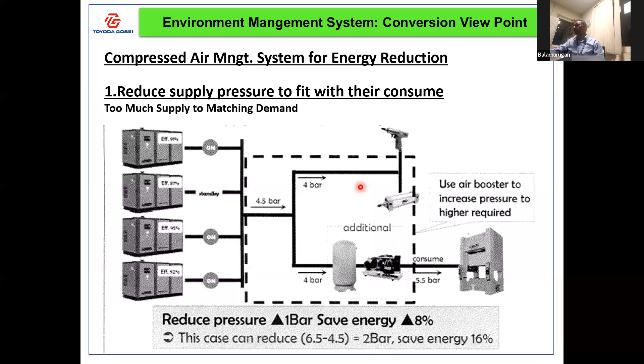So only for that equipment you need a higher operating pressure, so that the load on the main compressor comes down. This will give big energy savings, and we have experience of 16% energy savings in air compressors. Usually when a plant expands at different locations, different compressors are laid, but how do you centralize it and make a main header and sub headers so that we can optimize the operating pressure and supply pressure? There will be big energy savings apart from the air leaks.